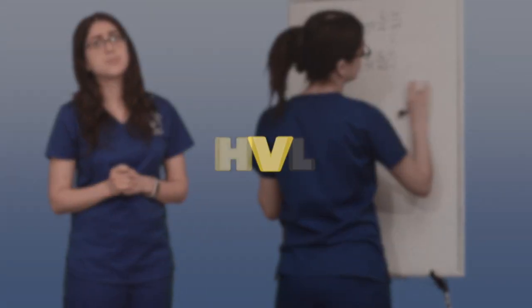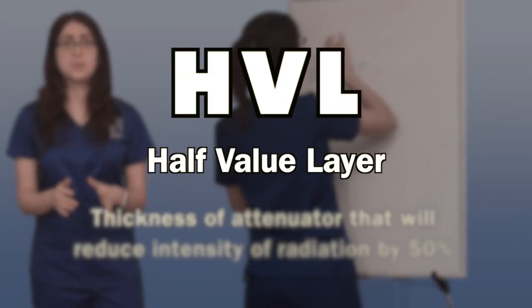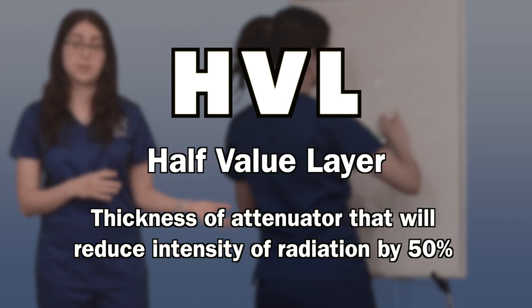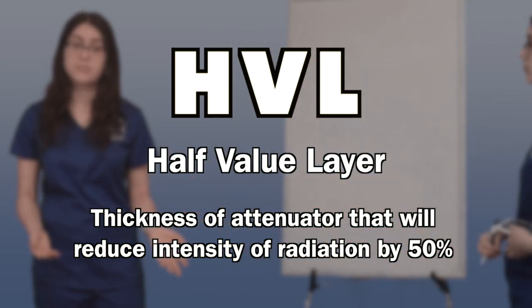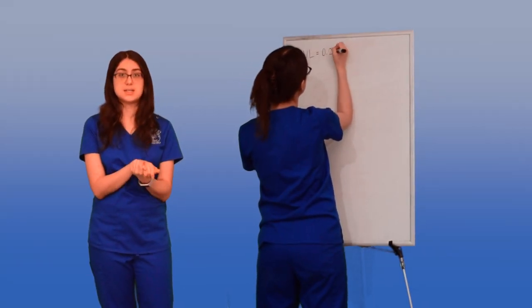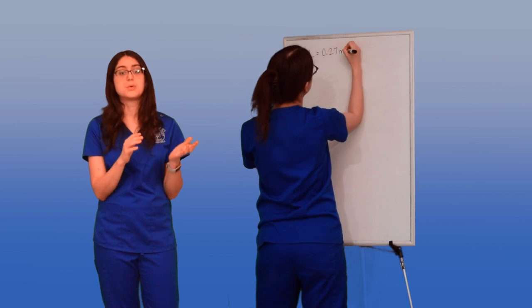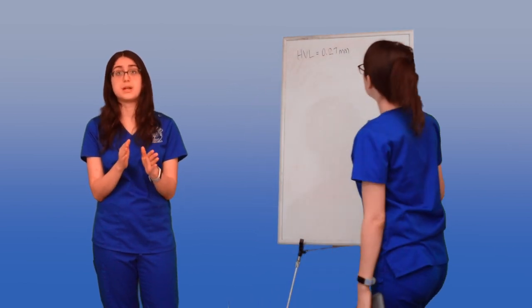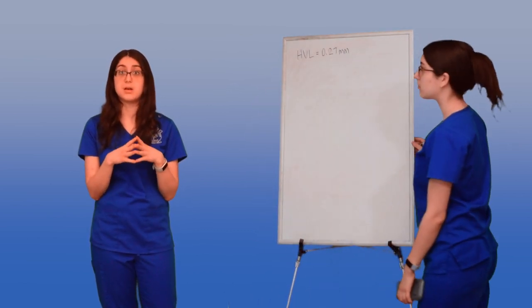Also, we can talk shielding. A half value layer is the thickness of an attenuator that will reduce the intensity of a beam of radiation by half. This is a set number for each attenuator for each radionuclide. I'm going to use lead as my attenuator, and I have technetium 99m as my radioisotope. The half value layer for this combination in particular is 0.27 millimeters.